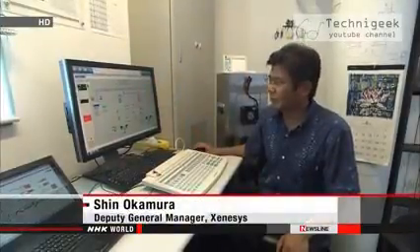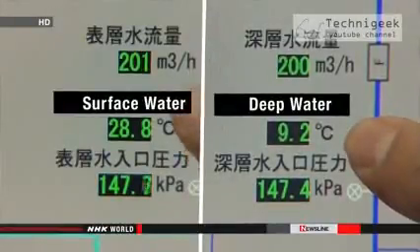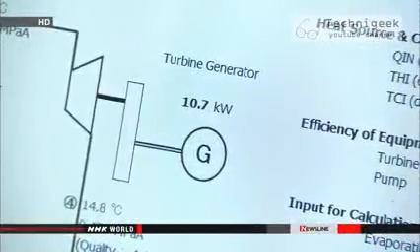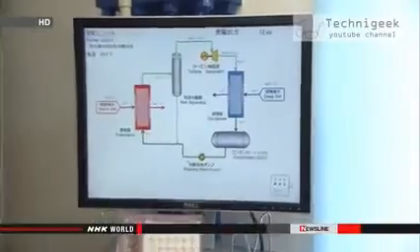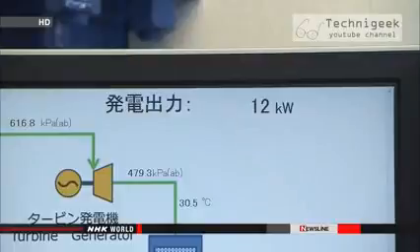The deep water is 9.2 degrees Celsius and the surface water is 28.8 degrees. According to our simulation, it should generate 10.7 kilowatts of electricity. In fact, the experiment went better than expected — it generated 12 kilowatts.